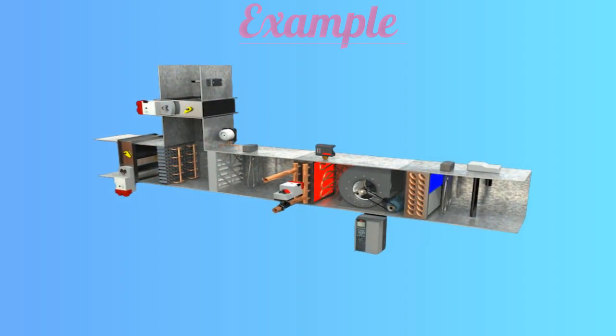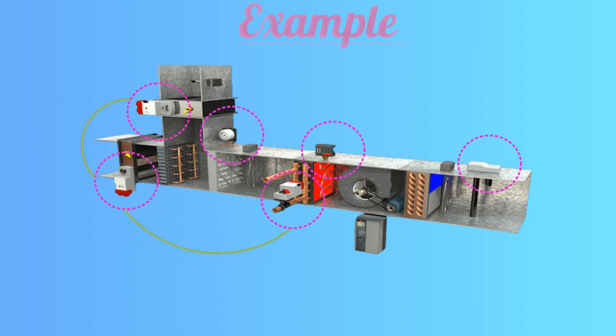For better understanding, look at the example on the screen. This is called an AHU — Air Handling Unit. You can see all the field devices are circled. These three are damper actuators: the first is installed on the fresh air, the second on the return air, and the third is installed as a valve actuator. This is a DPS — differential pressure switch — installed in the return line. This is a flow sensor. This is a temperature and humidity sensor, sensing temperature and humidity inside the duct.